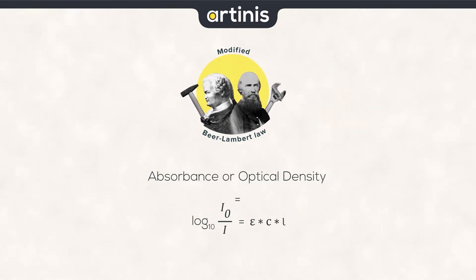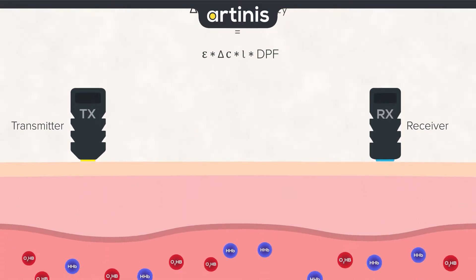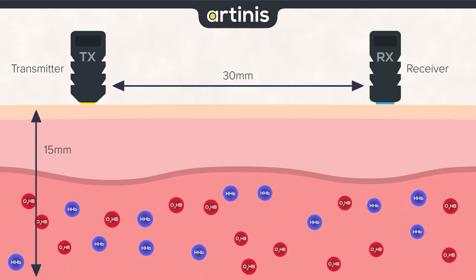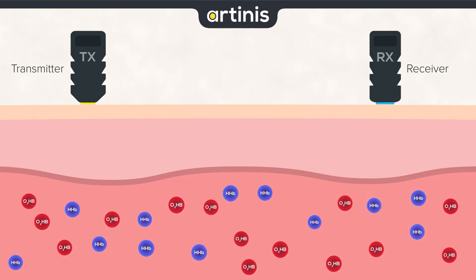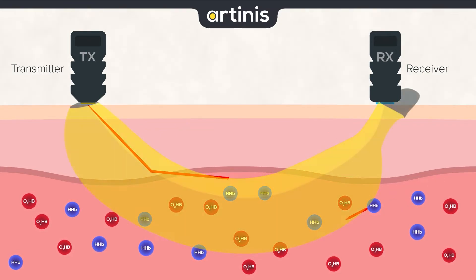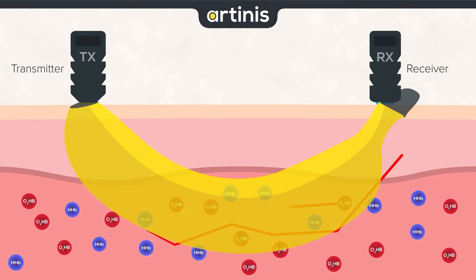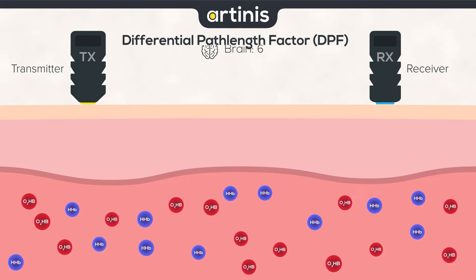How is it modified? We include a delta, so we measure a change, and we include a differential path length factor, or DPF. In this picture, we can see that a transmitter and a receiver are placed on the skin. In theory, a thin line of light goes from one to the other, but in reality this ray of light is more broad, or banana-shaped, with scattering happening in many places along the ray. To correct for these light losses, we include the DPF, which is a constant factor. For the brain, this is around 6, while for muscle research it is generally around 4.